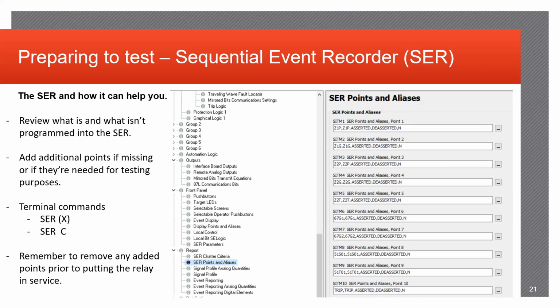This can be done usually during state simulation tests, where you'll be identifying an element that you want to show pickup, and you don't have a way of doing it through the software itself. You can implement any current voltage ratings, a dropout, have a contact open or close when need be, and record all that data through the SER.